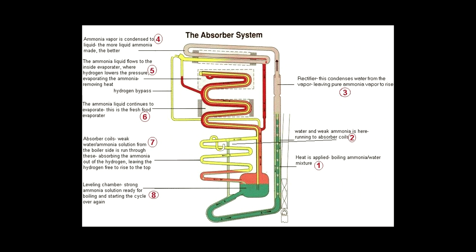A smaller tube comes off the large tube, then continues downward and goes into the evaporator coils. The smaller tube is actually a hydrogen bypass tube, so this allows the hydrogen gas to come off and recirculate back into the refrigeration loop near the absorber coils. While the liquid ammonia flows through the evaporator coils, it absorbs the heat from inside the refrigerator. This absorption of heat causes the ammonia to evaporate back into a gas.